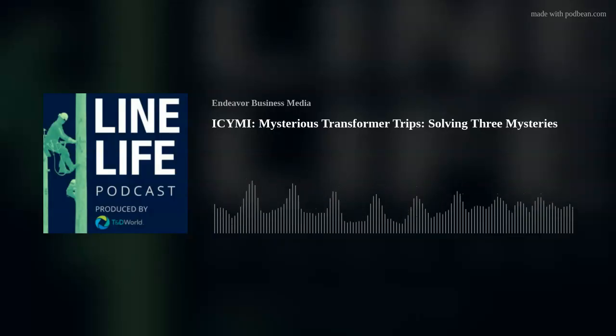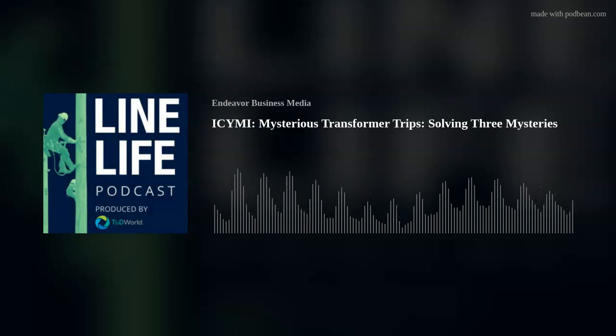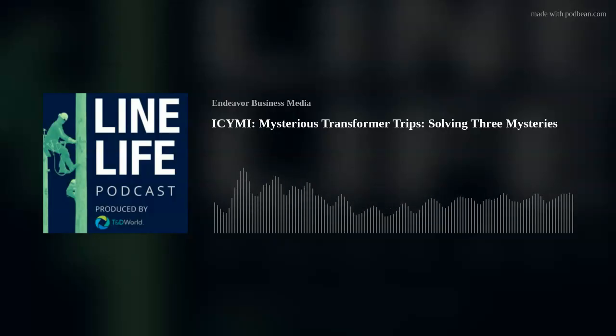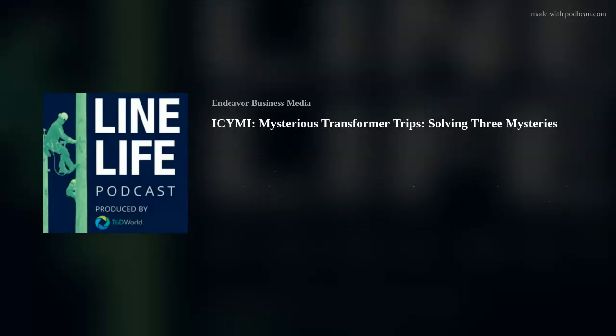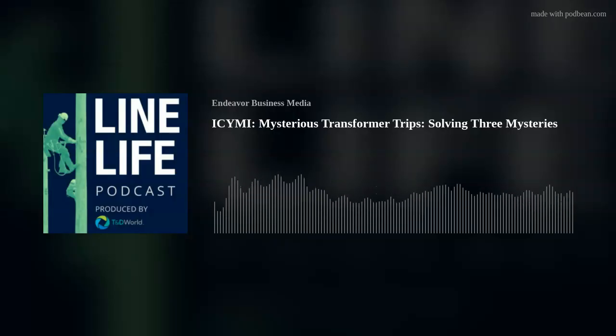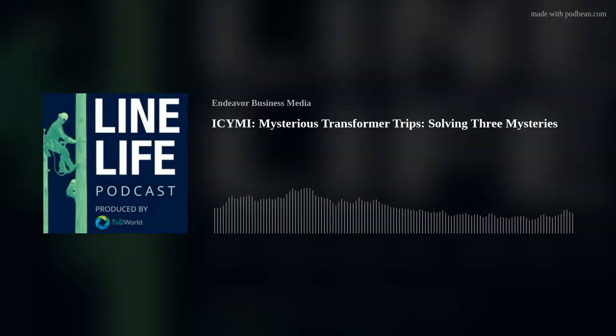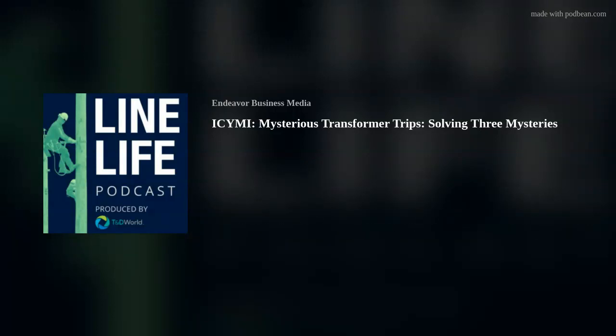Conclusion. Transformer trips are a common problem faced by engineers and technicians in the field. They can be caused by various factors, including weather conditions, faulty wiring, damaged insulation, and malfunctioning protective devices. In many cases, identifying the root cause of the problem can be a challenging task that requires a thorough investigation of all possible scenarios. As demonstrated by these examples, the process of troubleshooting transformer trips involves a combination of technical expertise, attention to detail, and persistence, lots of it.